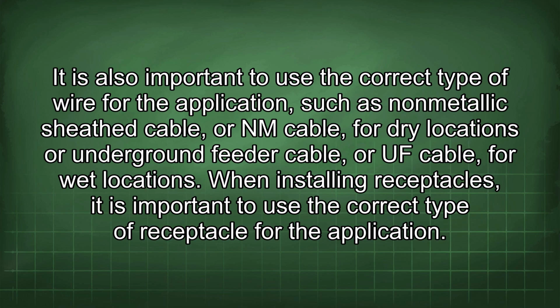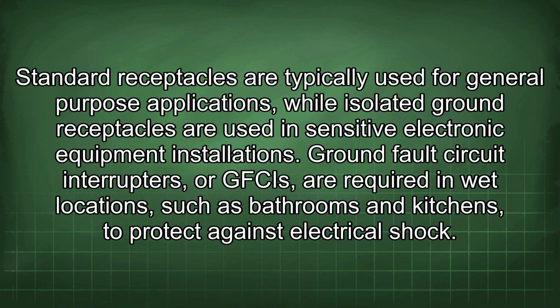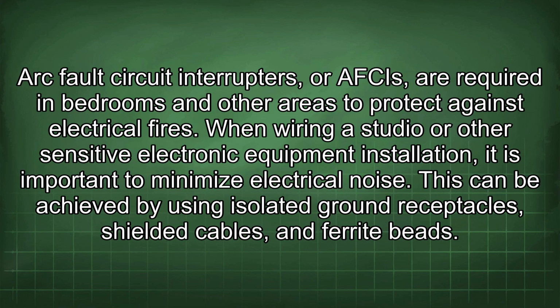When installing receptacles, it is important to use the correct type of receptacle for the application. Standard receptacles are typically used for general-purpose applications, while isolated ground receptacles are used in sensitive electronic equipment installations. Ground fault circuit interrupters, or GFCIs, are required in wet locations such as bathrooms and kitchens to protect against electrical shock. Arc fault circuit interrupters, or AFCIs, are required in bedrooms and other areas to protect against electrical fires.